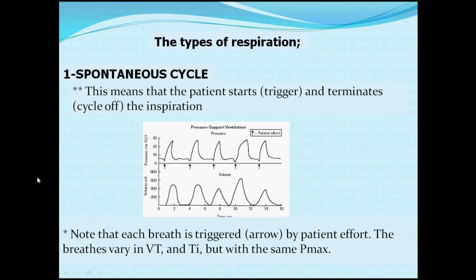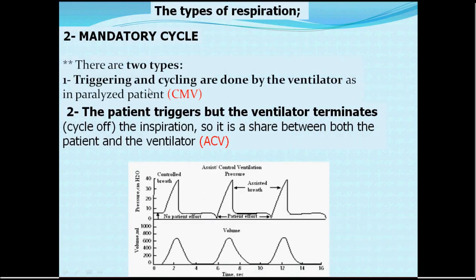Regarding types of respirations, we divide modes into spontaneous or mandatory. In spontaneous respiration, the patient triggers and terminates the cycle — so it is called a spontaneous cycle. Mandatory respirations have two subtypes: in controlled mandatory ventilation, both triggering and cycling are done by the ventilator, as when the patient is paralyzed. Alternatively, the patient may trigger while the ventilator terminates the cycle — as in volume-controlled mandatory ventilation where the patient starts the breath but the ventilator completes the cycle.